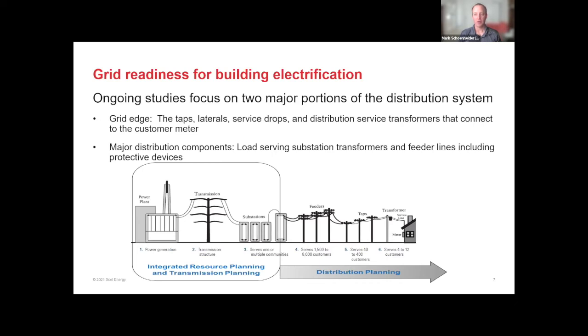Meeting that with all electric, so either a heat pump or electric resistance, you're going to need more electricity coming in. If you had the same efficiency on the peak summer day as you do on the peak winter day, you could get by with a 6-ton unit, but you don't, right? Air source heat pumps, by definition, their efficiency gets worse as it gets colder. There are quite a few good cold climate heat pumps now that may be able to keep up with the load down at 0 and 10 and 15. And our utility design day for winter is 25 degrees below 0.